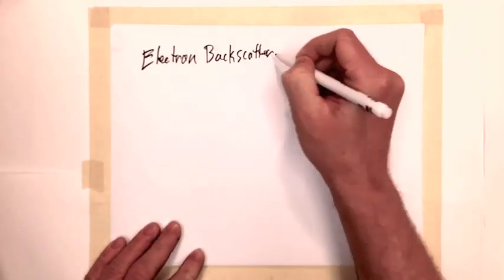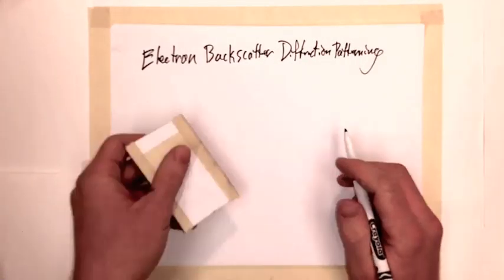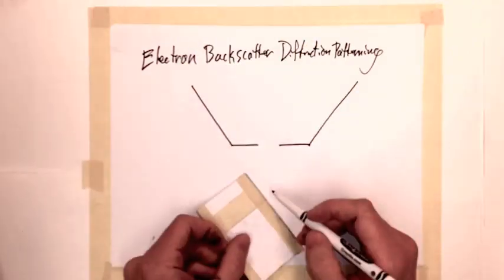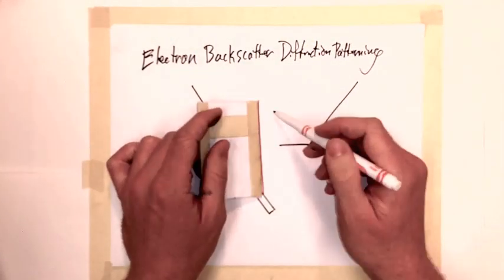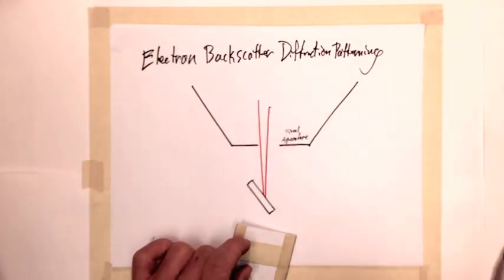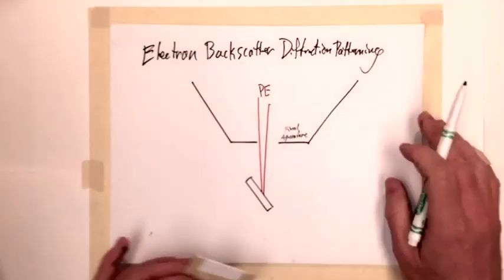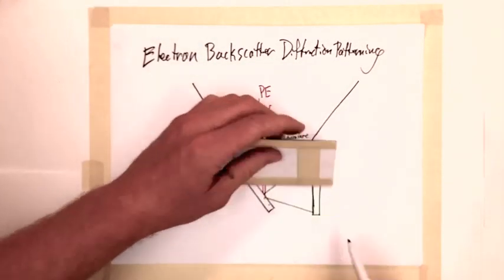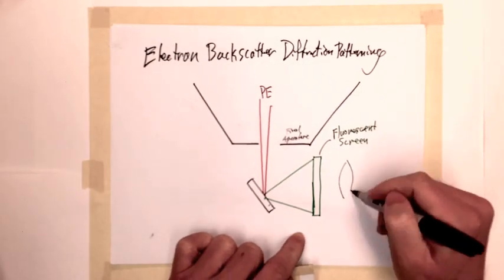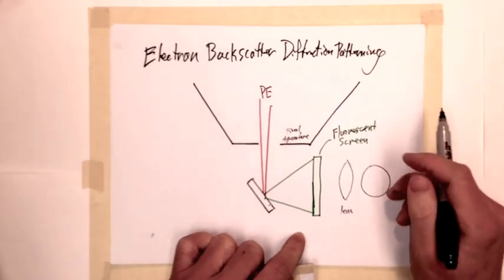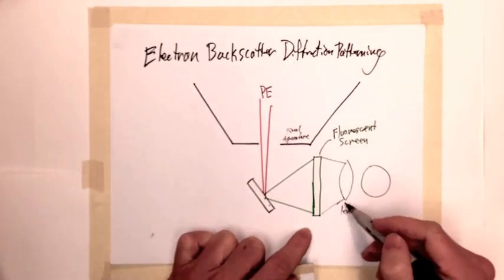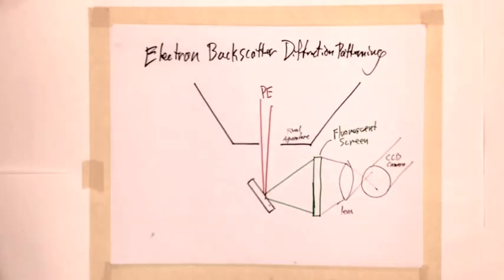The wave interaction of backscattered electrons with crystalline structures can be imaged as diffraction patterns in the SEM. The primary electron beam is held in place over a tilted sample while backscattered electrons are collected over a large solid angle. Diffraction pattern detectors use a fluorescent screen to detect electrons and produce an optical signal.